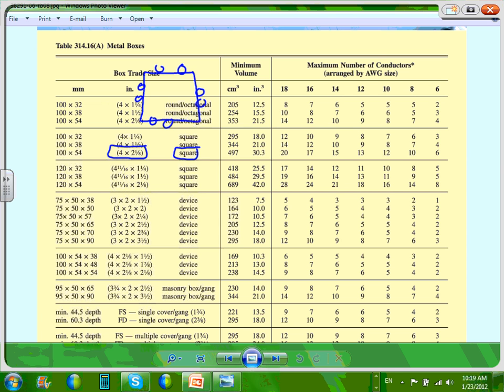This is very, very powerful in commercial, guys, because you're using it in the ceiling as a J box. Look what happened. When you have the J box, all of them are number 12. 99% of the J boxes in commercial are number 12. How many conductors can I bring to a J box? Typical 4 by 2 1/8, typical J box in the ceiling, 13. Look what that 13 can give you. All the equipment grounding conductors count as 1, so I don't have to count them. If you take 1 as the equipment grounding conductor, that will leave you with 12 conductors.